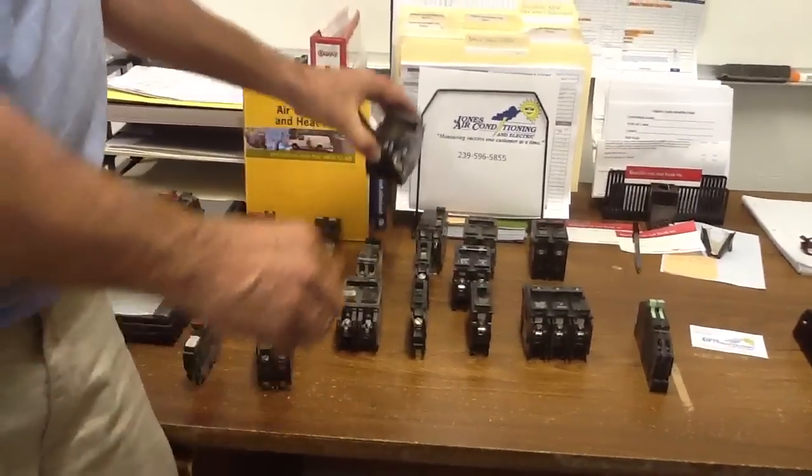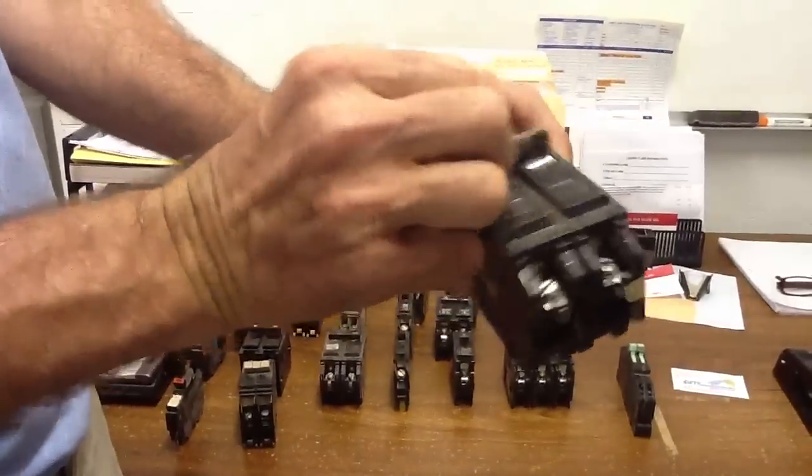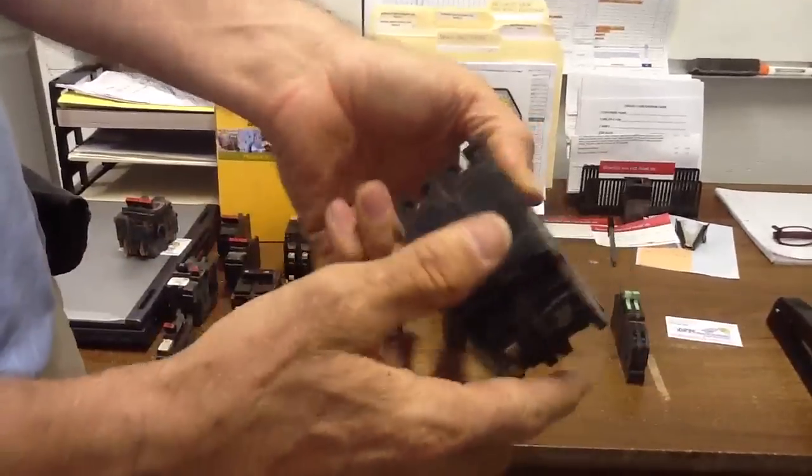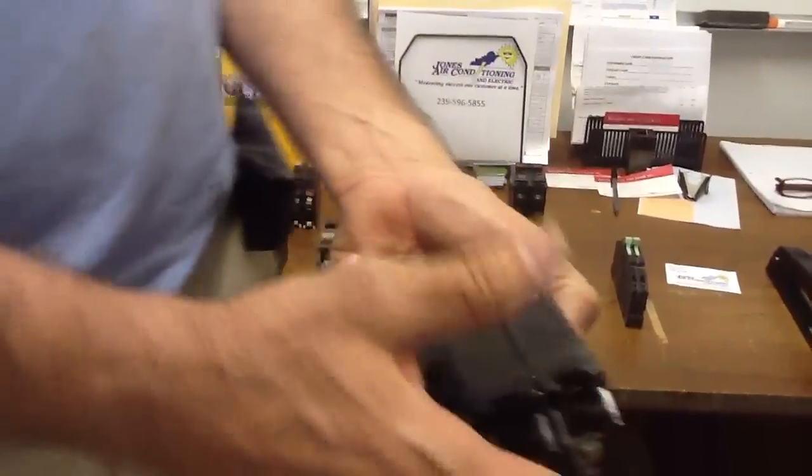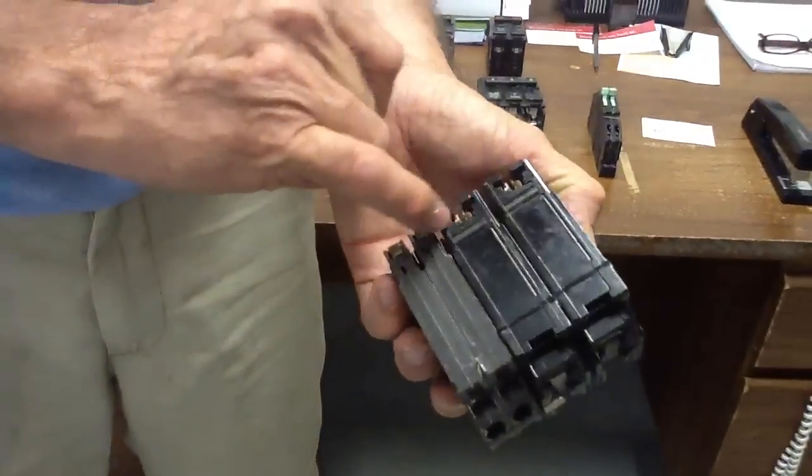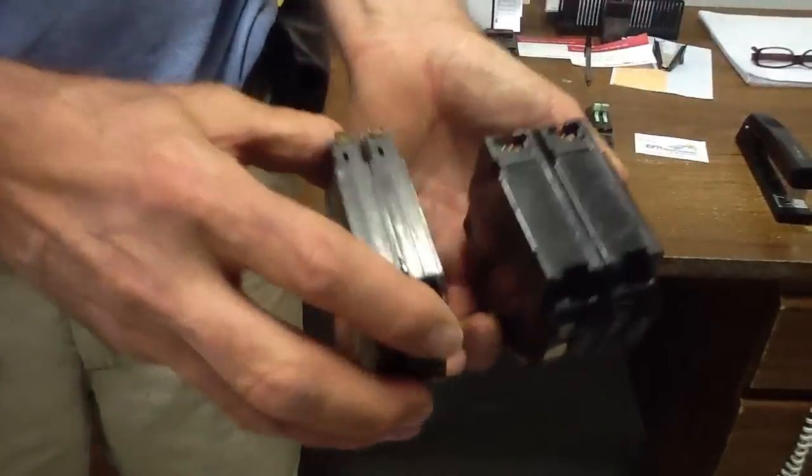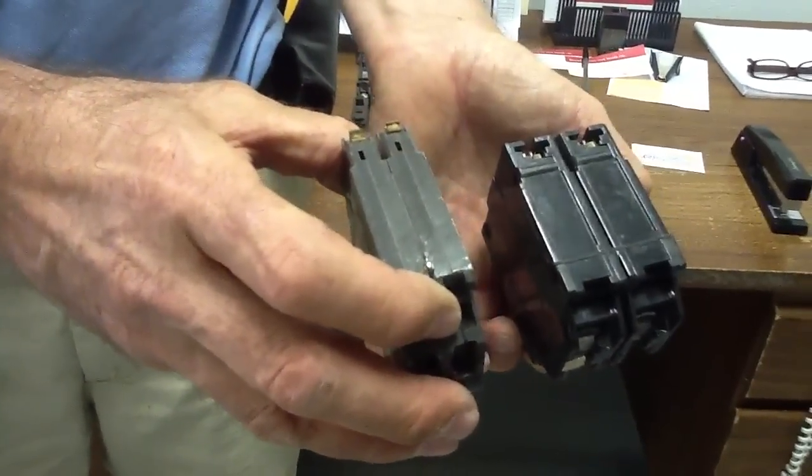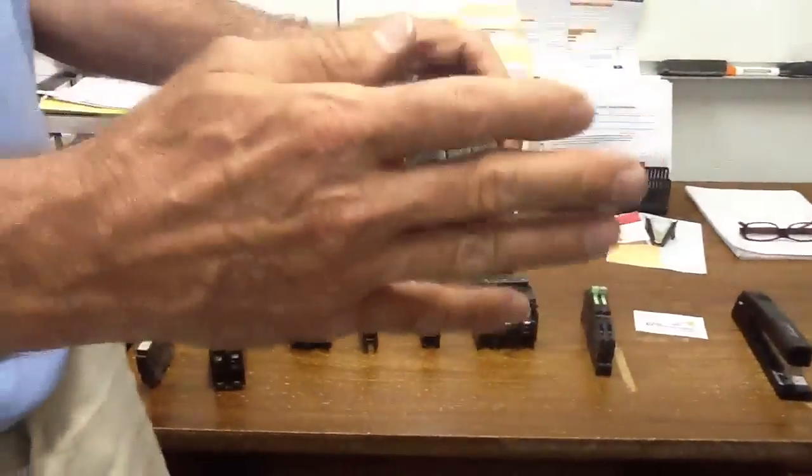This next one is a General Electric breaker, double pole. There's the footprint. Here is the thin General Electric. If you look at the stab locks, they're pretty close in size, but one's horizontal and one's vertical stab. The thin one is what I'll say is the horizontal, and the vertical is the fat one. They will not interchange with no one, which is what we want.